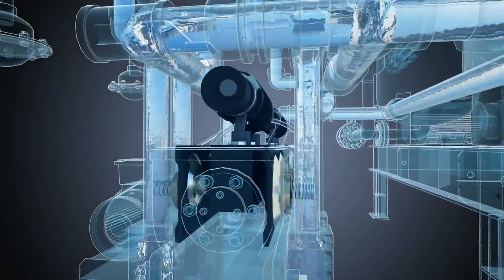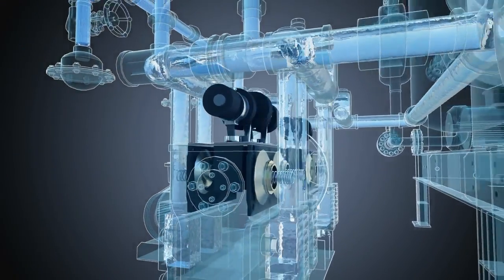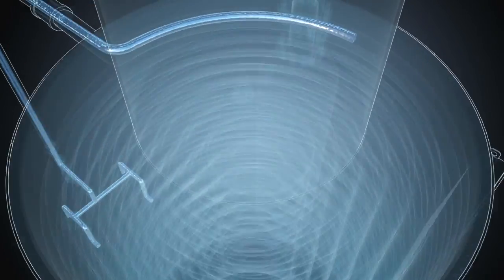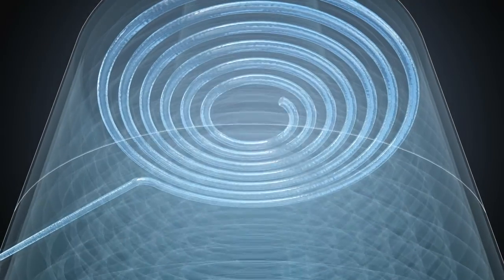In addition to a counter-flow heat exchanger, another unique design feature is that we control the water flow through the unit in sync with the firing rate, instead of allowing the water to flow by natural circulation.